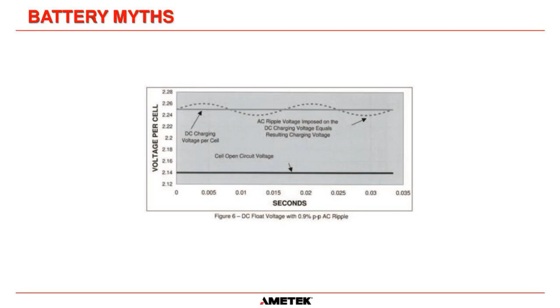And the thing to remember is, as long as your ripple does not go below this value, then your battery will not be discharging. Between this point here and this point here, your battery isn't discharging, okay? It's only when you go below this open circuit voltage that you start discharging your battery. Between this portion here and this portion here, that's only the difference between your charge voltage and your open circuit voltage. It's not discharging. Okay, so as you can see, the bottom ripple point there is going nowhere near our open circuit voltage, so this is not a problem.